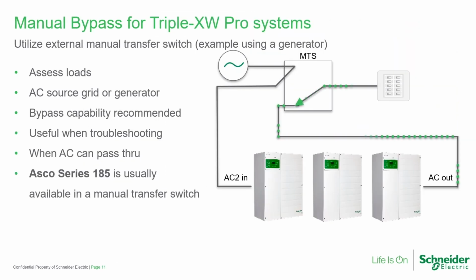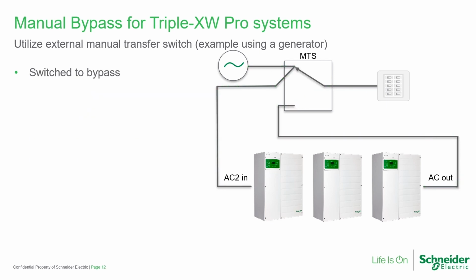If a load assessment reveals the switched current will not be detrimental to the transfer relays, then a manual bypass switch is recommended since there is no bypass interlock plate for a triple inverter system. Here is the system in normal operation. And here is the system switched to bypass.